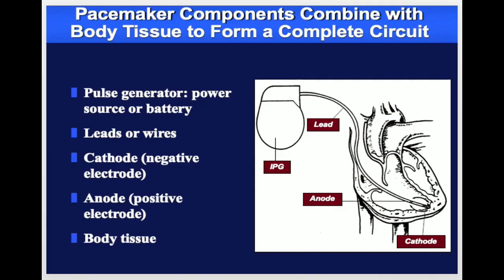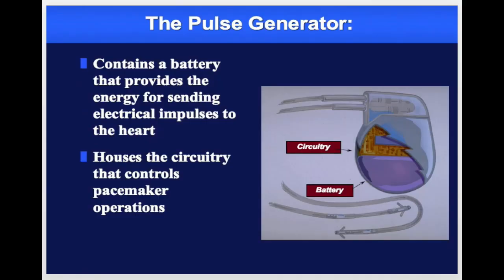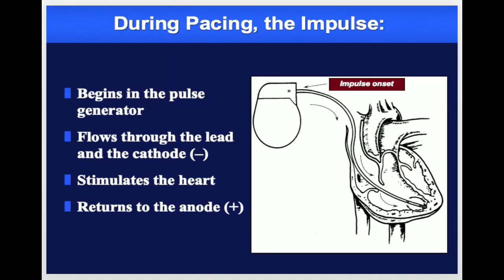The pulse generator is a foreign device which completes its circuit in combination with the body tissue with the help of the pulse generator, lead wires, cathode, which is a negative electrode, anode, which is a positive electrode, and body tissue. The pulse generator consists of a battery. This battery is made up of lithium iodide, the most commonly used power source for today's pacemakers, and microprocessors, both ROM and RAM, and control sensing, output, telemetry, and diagnostic circuits. During pacing, the impulse begins from the pulse generator, flows through the lead and the cathode, that's a negative electrode, stimulating the heart, and returns to the anode, that's a positive electrode.